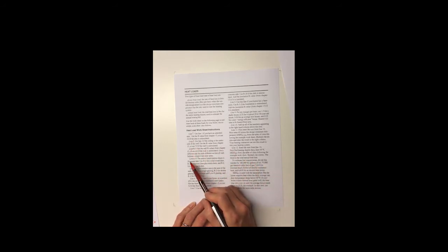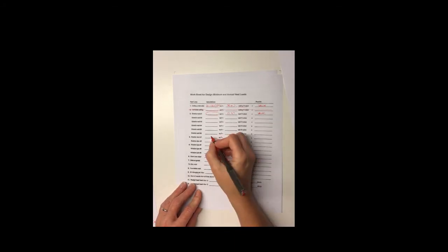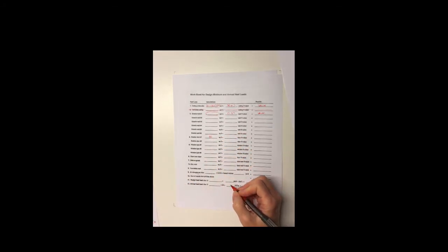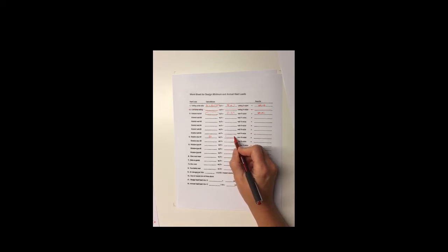this table here, so we've talked about line 1 and line 2 and line 3. Line 4, it says the area of most exterior doors is 20 square feet. In this case, we had 2. Use R2 for a solid wood door and R3 for a wood door plus a storm door, and an R6 for an insulated door. And so you can choose any one of those exterior door values that you want. We know that that exterior door is 40 square feet. And we then plug in whatever R value it is you're going to use for that, and we get another value here.